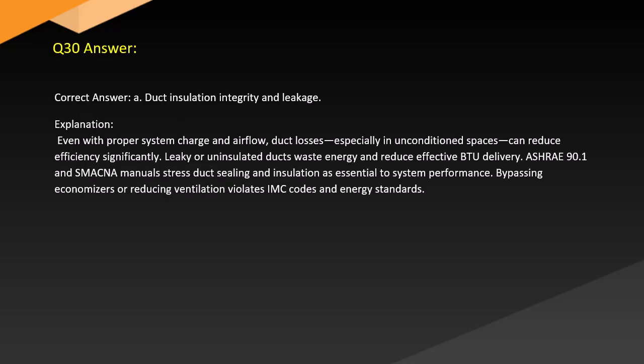Answer. Correct answer: A. Duct insulation, integrity, and leakage. Explanation. Even with proper system charge and airflow, duct losses, especially in unconditioned spaces, can reduce efficiency significantly. Leaky or uninsulated ducts waste energy and reduce effective BTU delivery. ASHRAE 90.1 and SMACNA manuals stress duct sealing and insulation as essential to system performance. Bypassing economizers or reducing ventilation violates IMC codes and energy standards.